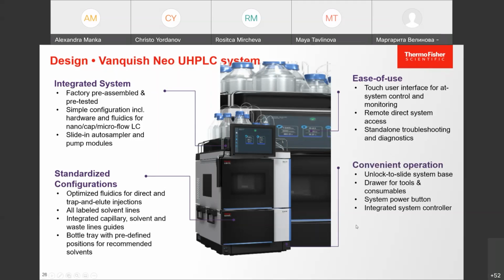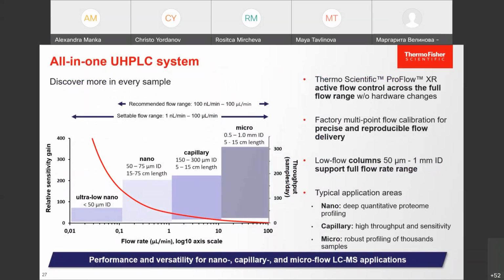On the bottom of the system, you have this unlock-to-slide system base, so you can move the system very easily. You have the drawer for some tools and consumables. You have one system power button and an integrated system controller with the Vanquish Neo system. As said, this is an all-in-one UHPLC system for nano, capillary, and microflow. The settable flow range goes from 1 nanoliter to 100 microliter, but our recommended flow rate is 100 nanoliter to 100 microliter. This is possible with our new ProFlow XR active flow control in the system. It's factory calibrated already for precise and reproducible flow delivery, and it's designed for low flow columns from 50 micrometer to 1 millimeter ID.